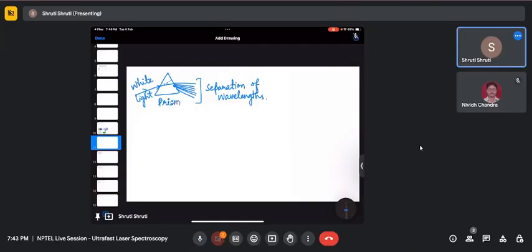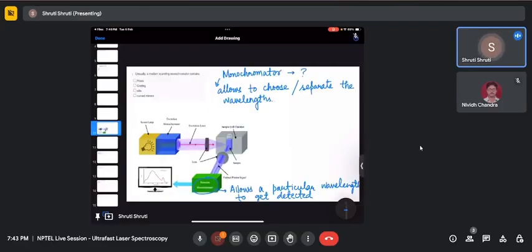So basically, the idea of adjusting the slit width in any experiment has to do with the wavelength resolution. There will be options in the fluorimeter like 1 nanometer, 2 nanometer, 8, 16, 32. 32 is way too big a slit width. So we generally keep it at max up to 5 nanometers. Basically slit width has to do with the resolution only, nothing else.